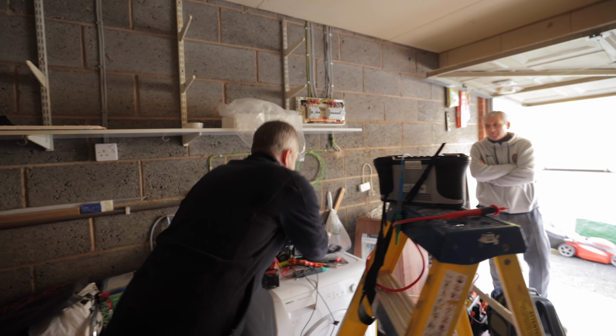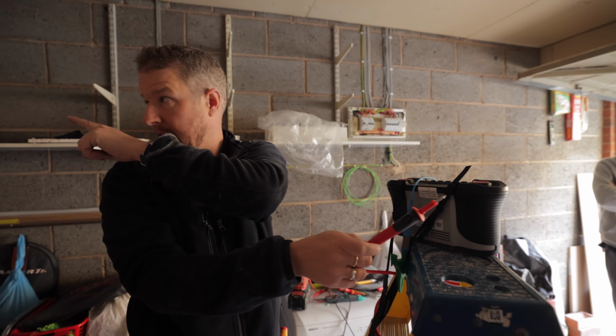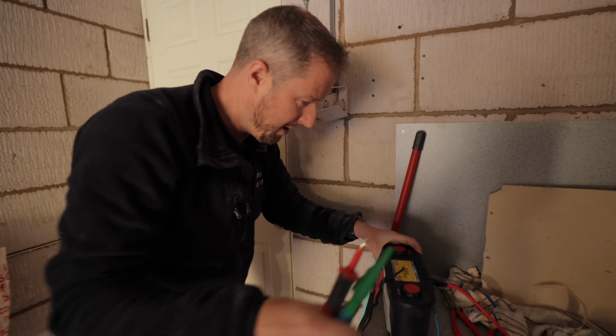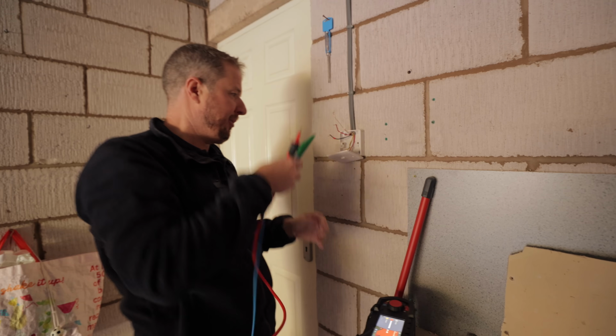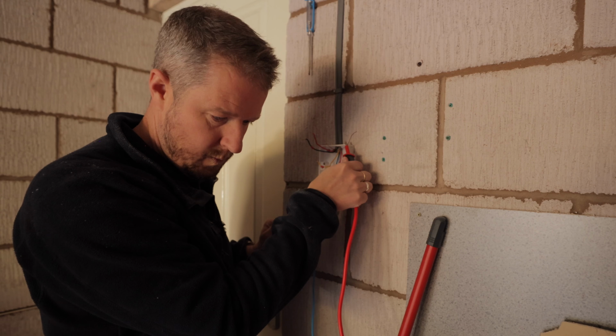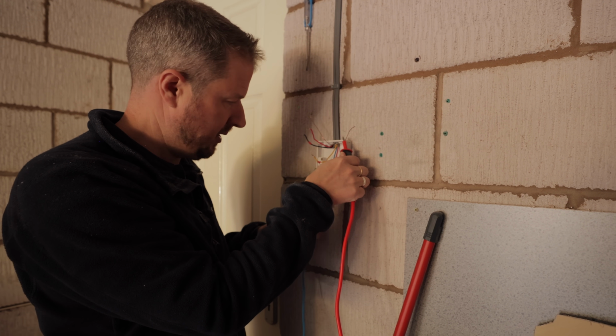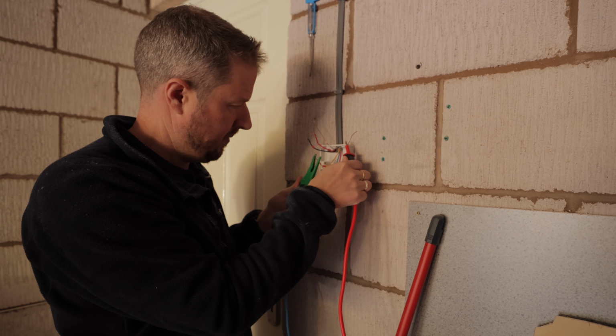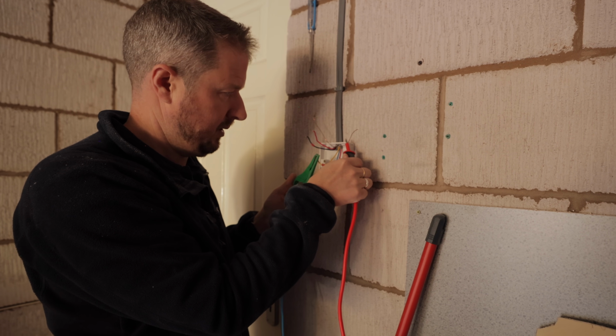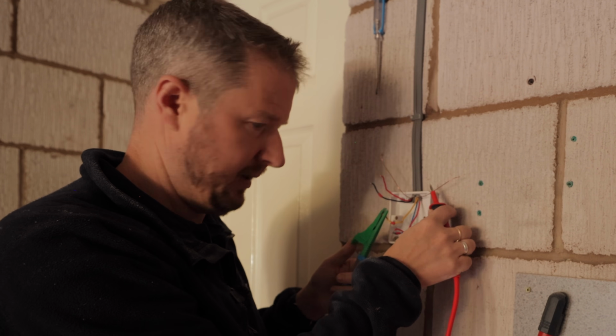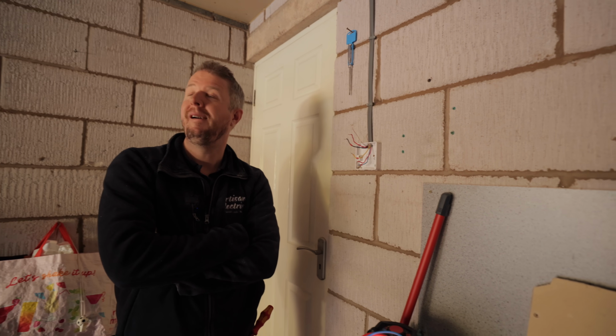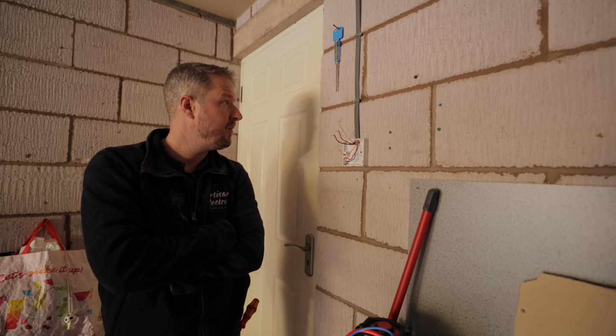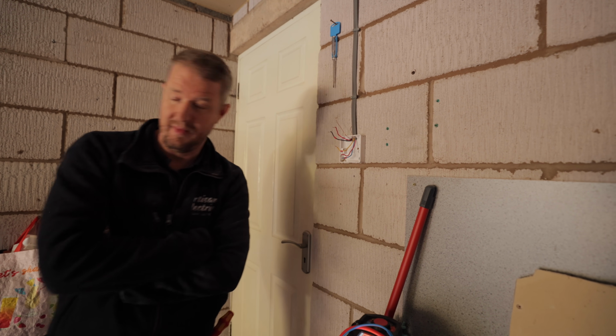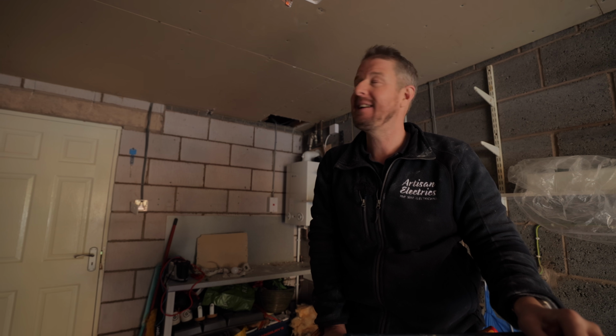I've got an idea. Now what we're going to do is an insulation test on that cable that goes from there to there. And I've got a feeling we might find a problem with that cable. So that one's all good. That one's all good. That one's all good. That was not what I was hoping to find. My cable seems fine. I don't get it. It must be a nail or a screw or something. That's all it can be, surely, but I just don't understand because it tests out fine.